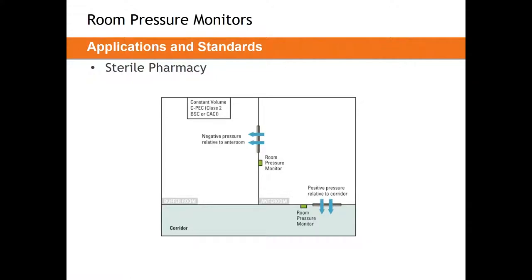The next type is a sterile compounding pharmacy. With sterile compounding, a few things change: we require 30 air changes per hour and we require an anteroom that is also 30 air changes per hour. Now that we have two spaces, we have a pressure cascade — pressure cascades from the buffer room to the anteroom and from the anteroom out to the corridor. The display goes right beside each doorway and the sensor right above the door. Measuring from corridor to anteroom and anteroom to buffer room is the most common approach.